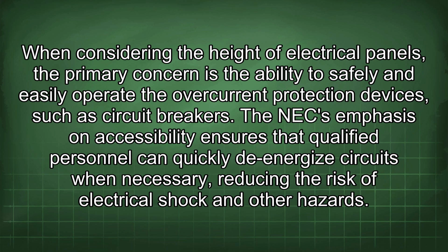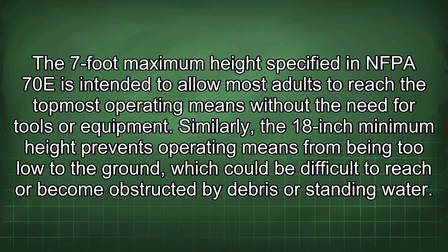The NEC emphasis on accessibility ensures that qualified personnel can quickly de-energize circuits when necessary, reducing the risk of electrical shock and other hazards. The 7-foot maximum height specified in NFPA 70E is intended to allow most adults to reach the topmost operating means without the need for tools or equipment. Similarly, the 18-inch minimum height prevents operating means from being too low to the ground, which could be difficult to reach or become obstructed by debris or standing water.